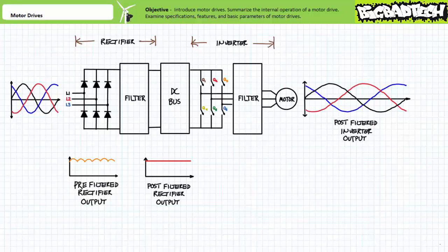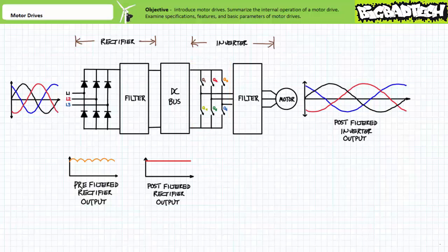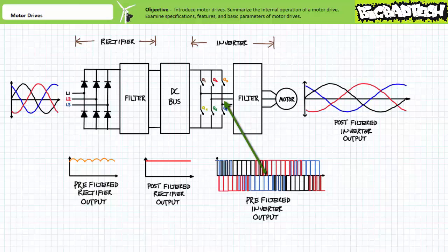The rectifier is an AC-to-DC converter that changes incoming three-phase AC with a fixed magnitude and frequency into DC. Ordinarily, the rectifier is a type of three-phase AC bridge rectifier that produces an output with an inherent ripple, which is removed with a filtration circuit that produces a relatively stable DC value. The other half of the motor drive — the inverter — can also be modeled as having two distinct stages: the inverter itself, which changes the incoming DC into three-phase AC with variable magnitude and frequency, and a filtration circuit that cleans up this stage's respective output.